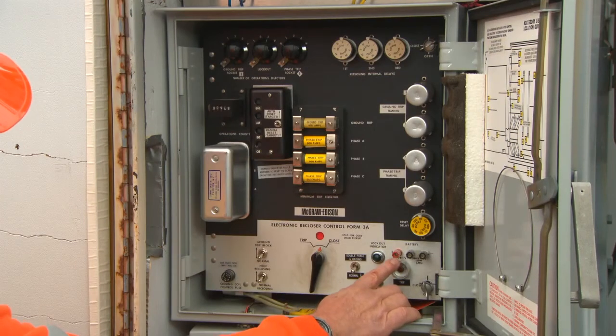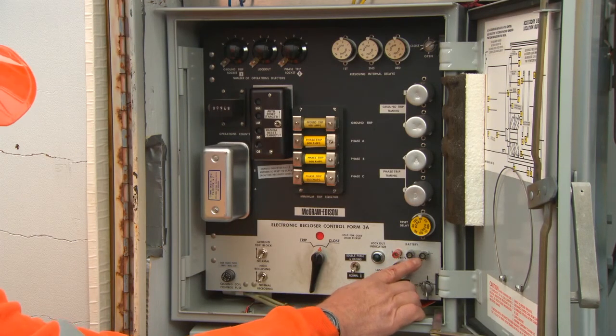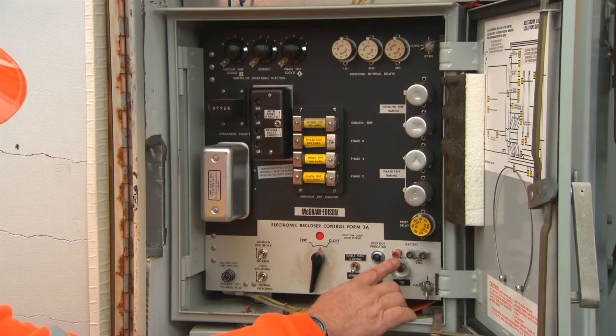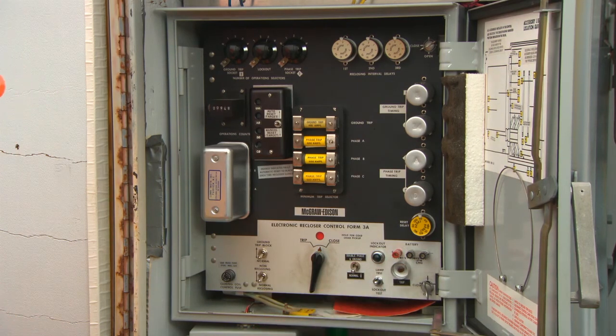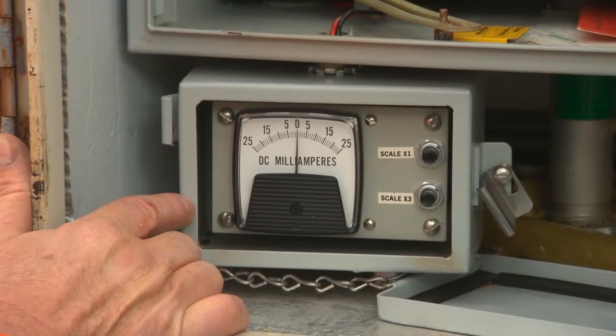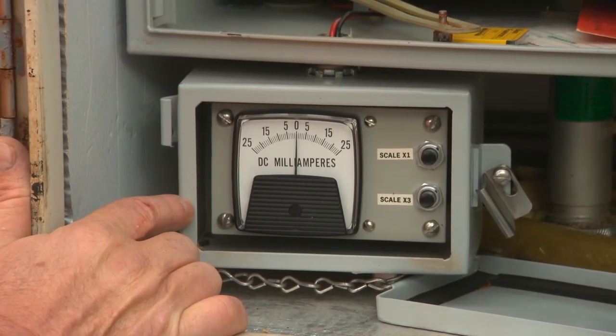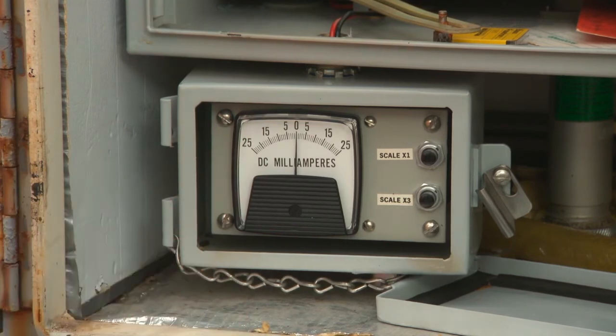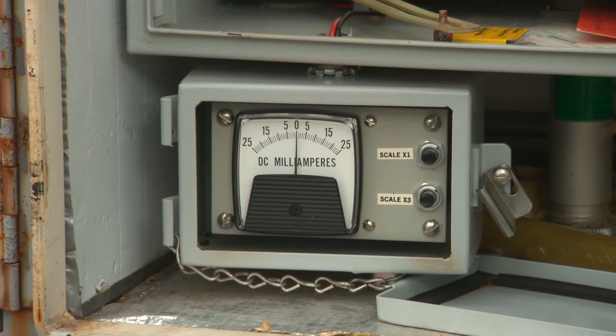Next are battery terminals. These can be used to test functionality of the batteries. The reclosers cannot be operated by the control panel in the automatic mode. If the battery falls below a certain threshold level, it will have to be opened manually. This is the DC milliamperes display. This shows that the battery is in a charged state. This indicates whether or not the charger is working.